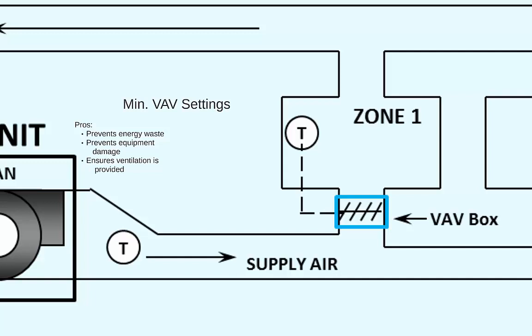We will talk more about how that is exactly done in the next lesson on ventilation, but for now just know that we obviously can't be bringing in ventilation air if we were cutting off all of the airflow into a space.